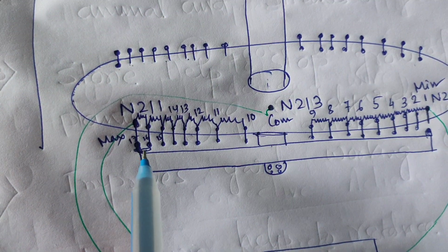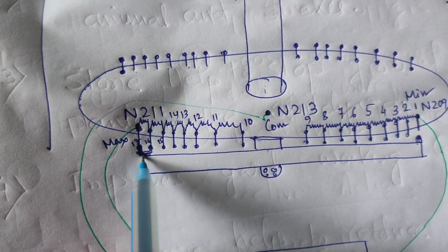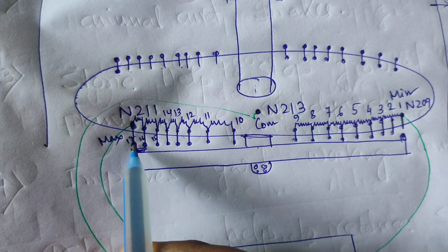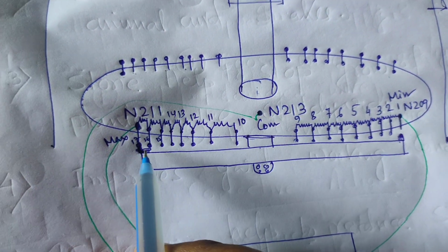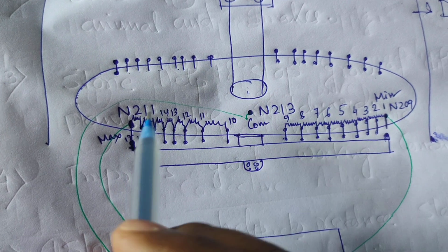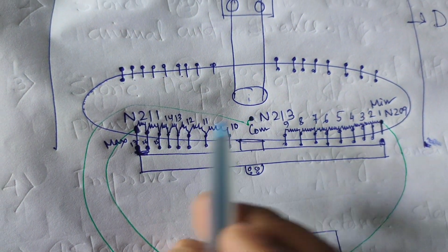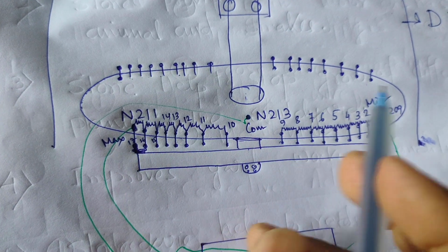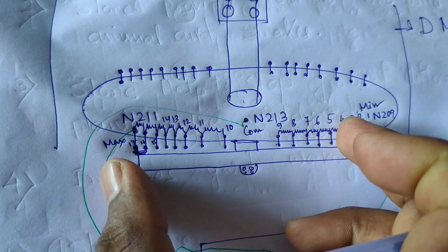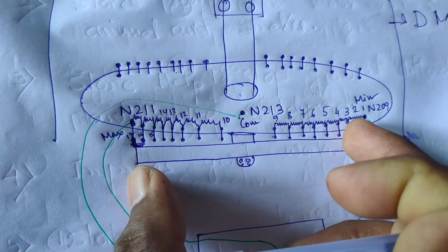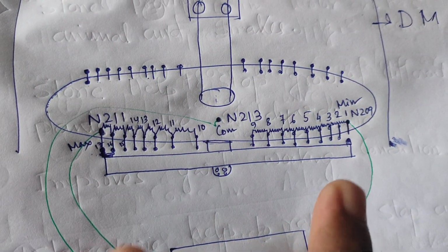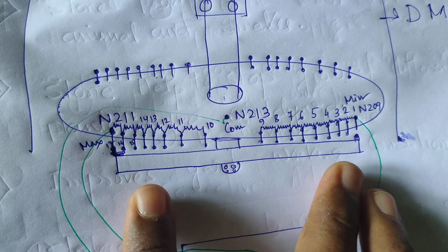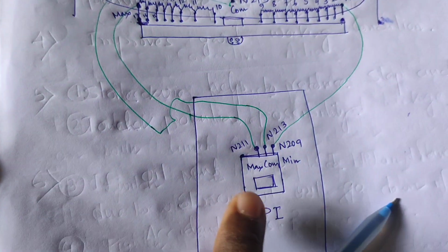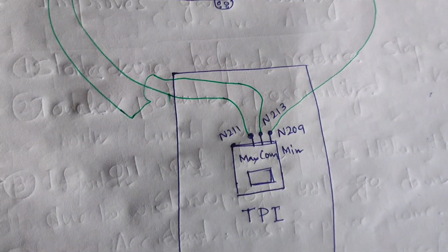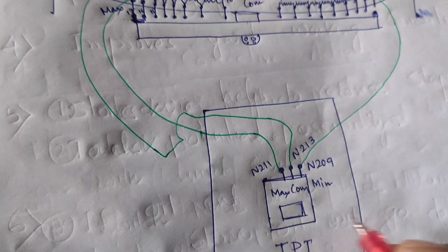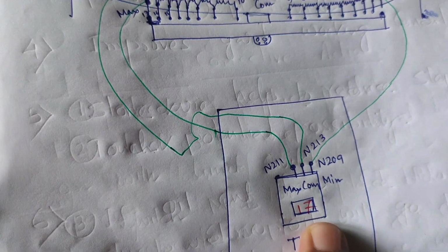That's why we are connecting this black color wire with the tap position or tap resistance. So what is the measurement here? The measurement here is the resistance of 1 to 17, the total resistance it is showing. If the resistance is 16.15 kilo ohm, it will be converted to tap number 17. Here it shows tap number 17.